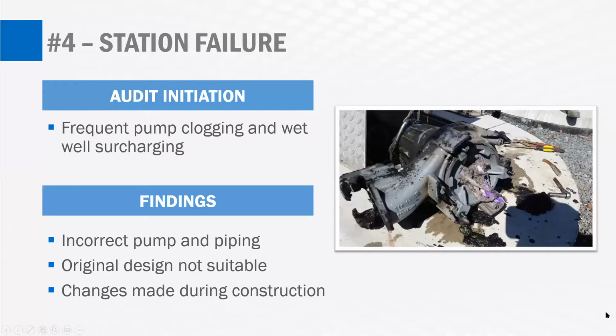So at the end of the day, the recommendation for this pump station was that all of the guts of the station had to be replaced, unfortunately. All the piping and valves, the pumps themselves, so that we had a suitable pump selection in here. And one of the other recommendations was to install a trash basket to deal with the debris that this pumping station was not going to be able to handle itself. Next slide.